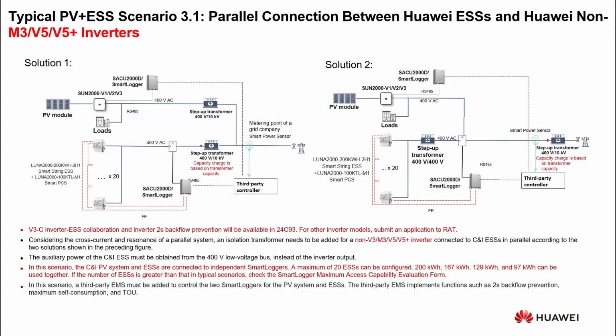We don't need this transformer. Also, if we don't use it together with third-party PV systems like the other brands, we don't need this transformer. And as well, if we don't need the off-grid mode, which in our case is mandatory for the battery to be equipped with an extra EMS system, not just the transformer, you also do not need this transformer. So this is a kind of flexibility which does not force the user to buy a part or component which is not very cheap. However, it's not mandatory in every scenario.